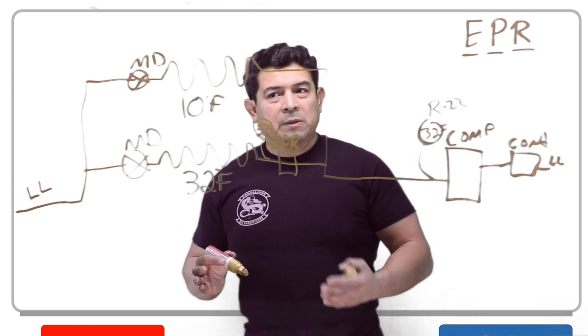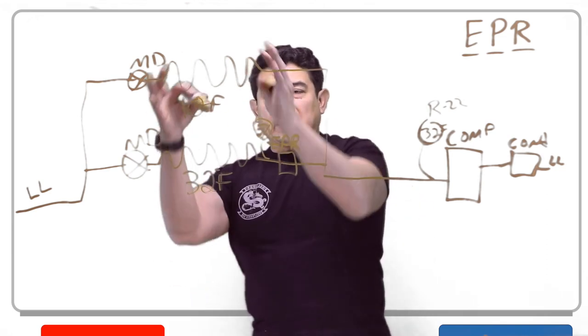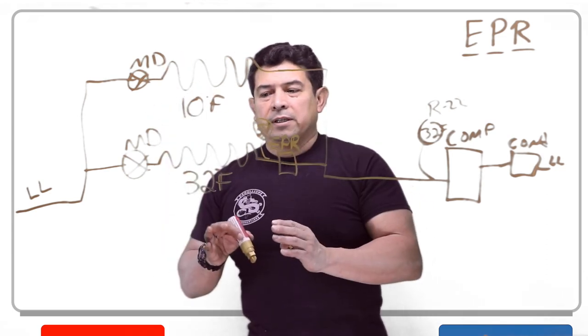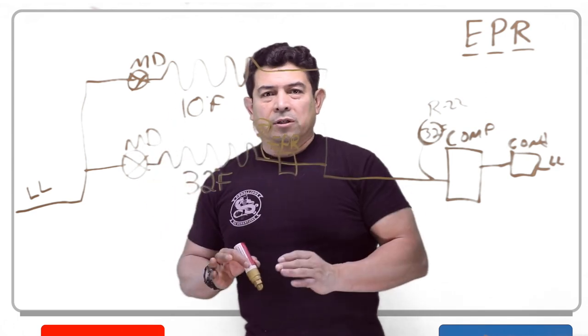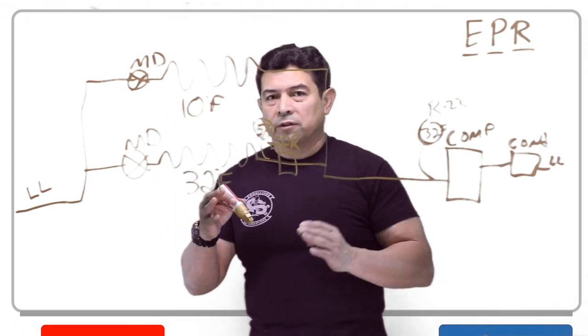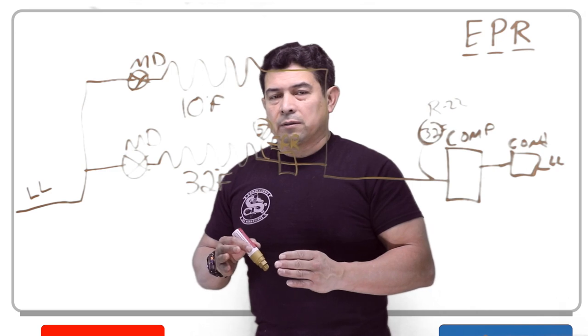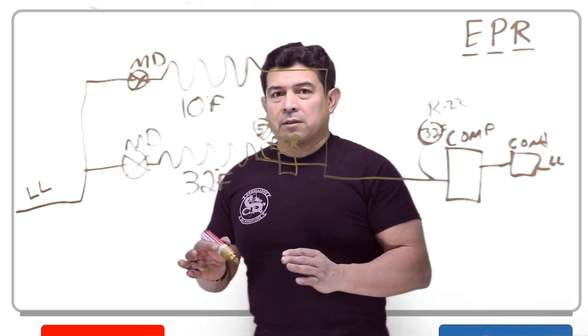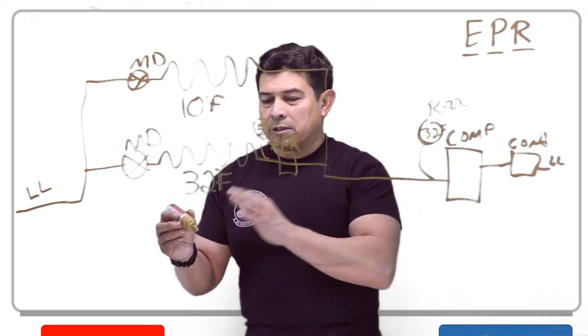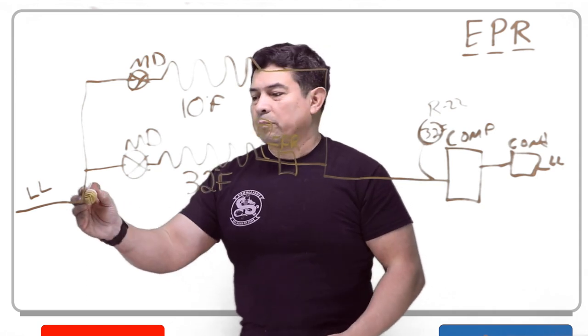Now this evaporator or box is going to be at 10 degrees Fahrenheit, and this one is going to be at 32. So we're maintaining two different temperatures. That's great because now the company is saving money - they don't have to buy too much equipment.